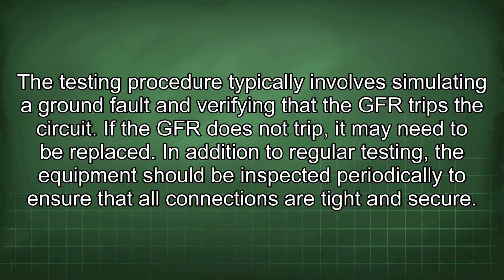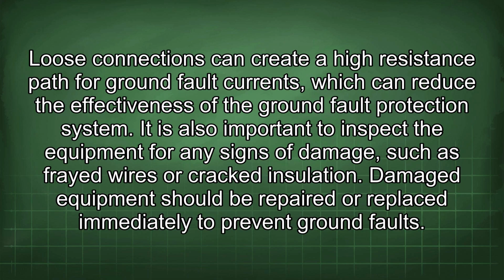In addition to regular testing, the equipment should be inspected periodically to ensure that all connections are tight and secure. Loose connections can create a high resistance path for ground fault currents, which can reduce the effectiveness of the ground fault protection system. It is also important to inspect the equipment for any signs of damage, such as frayed wires or cracked insulation. Damaged equipment should be repaired or replaced immediately to prevent ground faults.